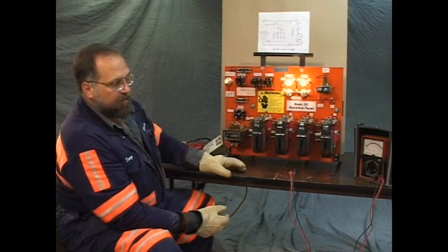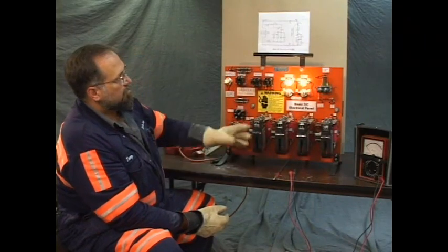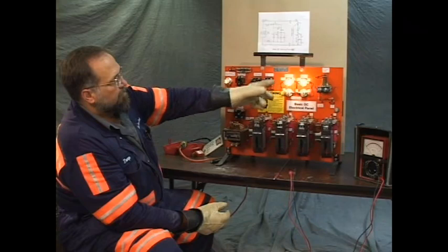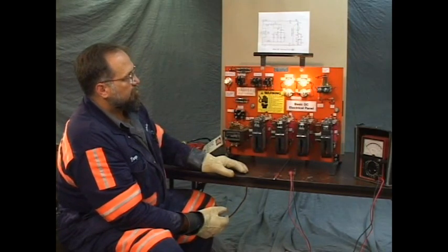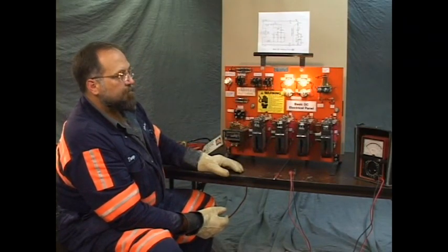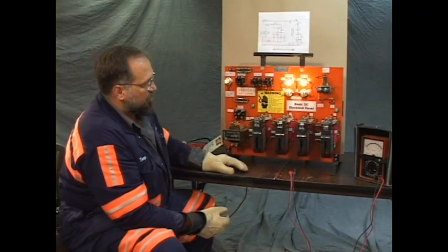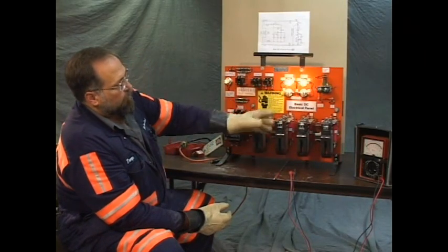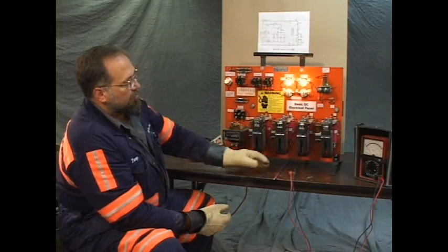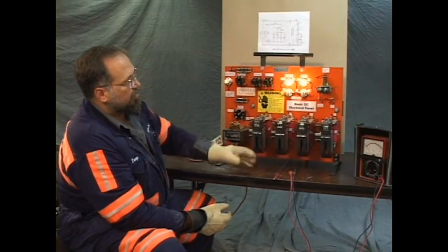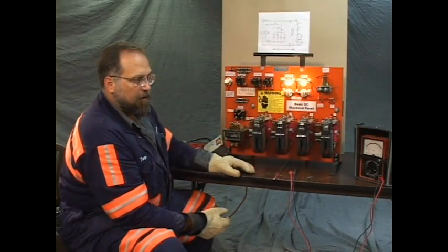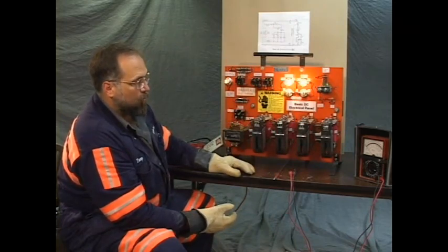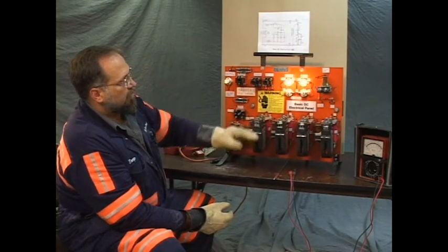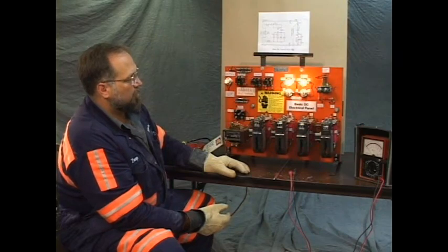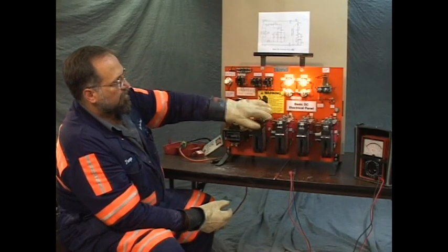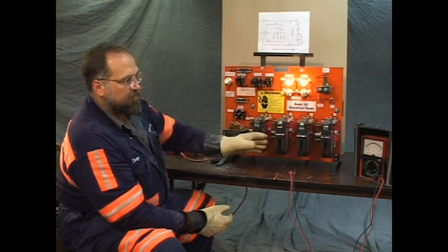The lights: the bottom left light never came on at all. The bottom right was dim. The top right was dim. The top left was bright. It performed normally. After 1 second, we had a contactor closed, 2A closed, and the bottom right light went off. That's normal for the 2A to close and the bottom right light to go off. Our malfunction was 1A contactor went in out of sequence.